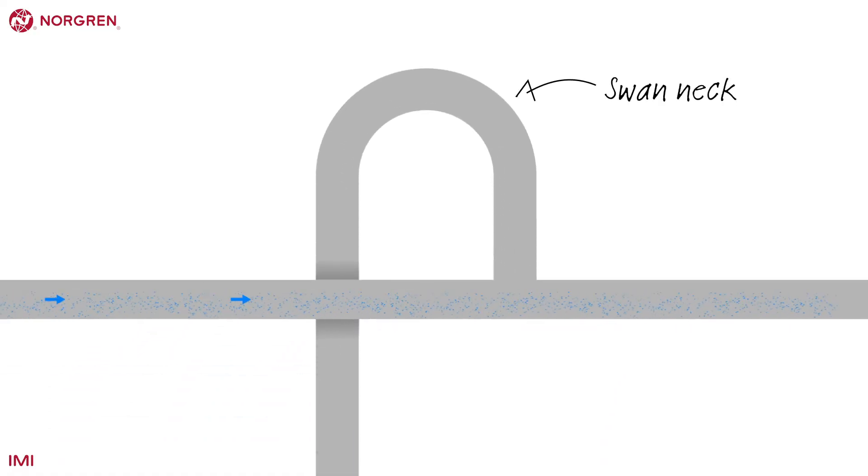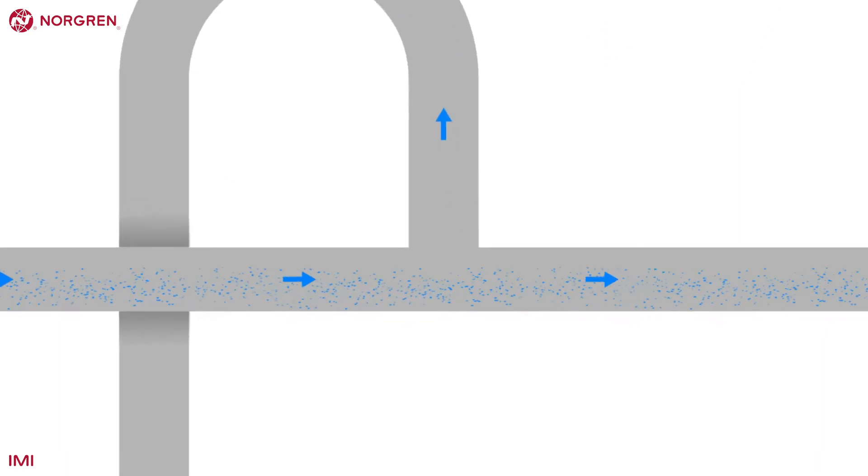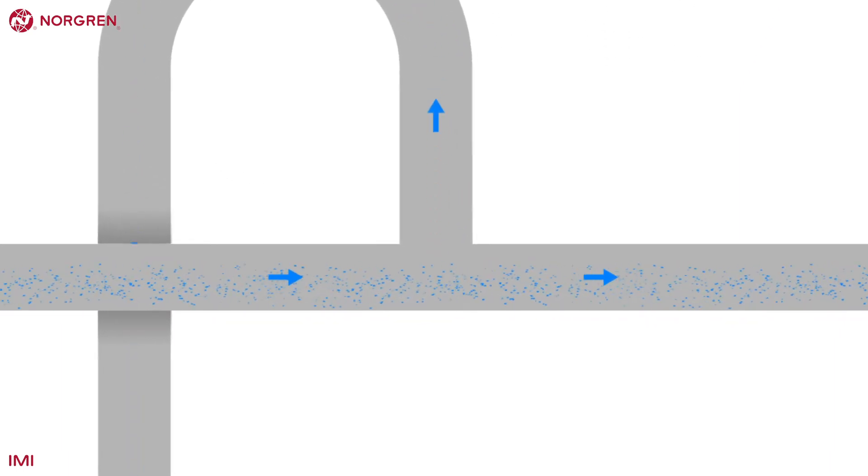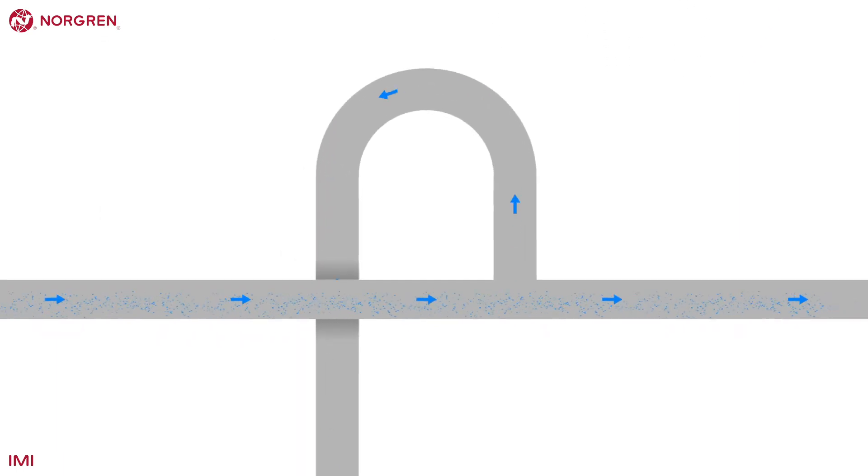Notice the swan neck that comes from the top of the ring main. Taking air from the top will inhibit any fluid entering the downpipe and the swan neck provides the smoothest route for the air. Hard angles or elbows will slow airflow.